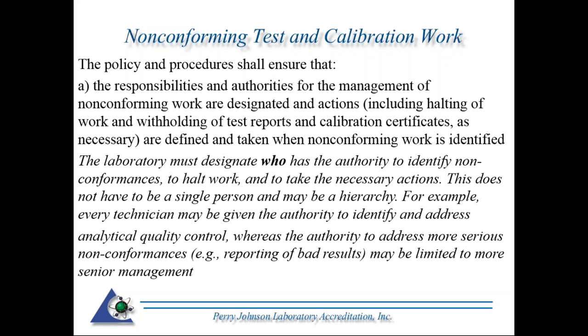Depending on the size of the organization, this does not have to be a single person. It may have a hierarchy. For example, technicians may be given the authority to identify and address analytical quality control, whereas the authority to address more serious non-conformances, such as reporting of bad results, may be limited to more senior management. Realize that for smaller organizations, you may have a two or three person calibration lab. In that case, this all may be the responsibility of one individual, regardless of the severity of the non-conforming work.